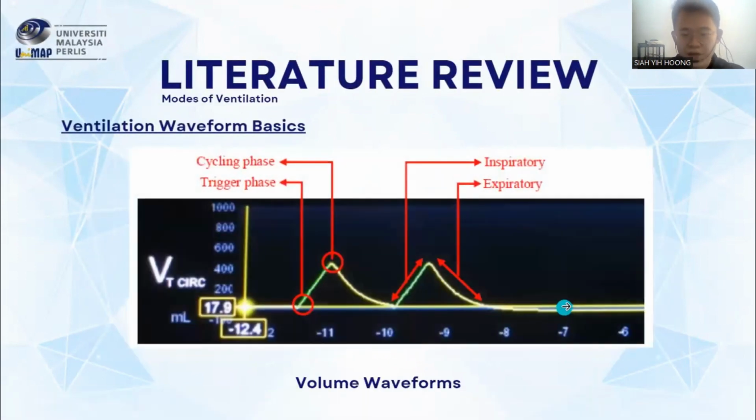For your information, traditional ventilators are actually controlled by two modes. The first mode is pressure. The second mode is volume. If we control by volume, we are manipulating the volume and sending it to the patients. If we control the ventilator by pressure, we manipulate the air pressure and send the air towards the patients. In this project, we apply a volume controlling method for this ventilator, so it is known as a volume control ventilator.